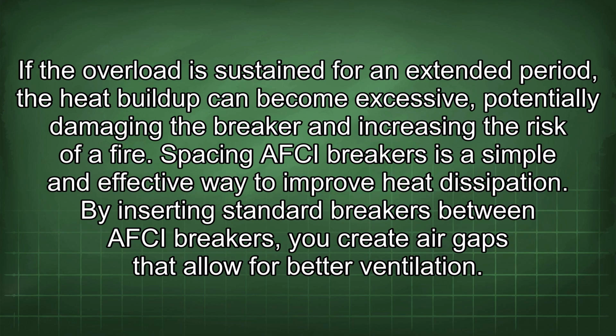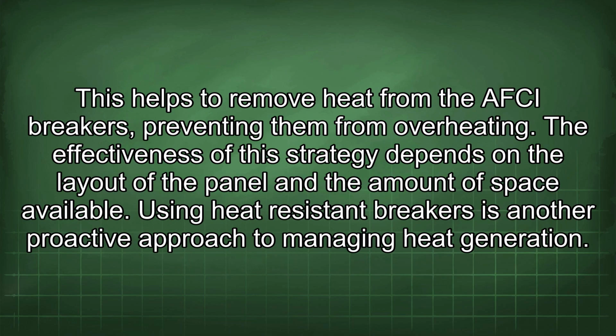Spacing of AFCI breakers is a simple and effective way to improve heat dissipation. By inserting standard breakers between AFCI breakers, you create air gaps that allow for better ventilation. This helps to remove heat from the AFCI breakers, preventing them from overheating. The effectiveness of this strategy depends on the layout of the panel and the amount of space available.